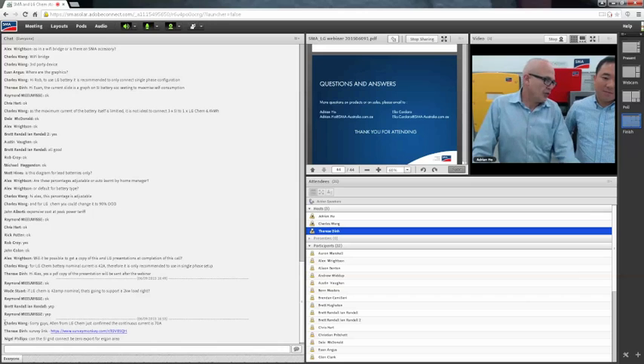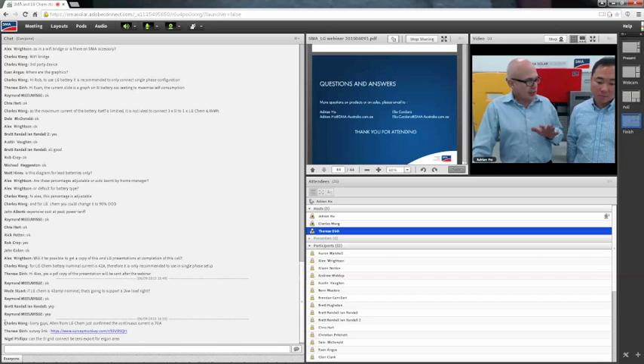On a 3-phase system, if you put a Sunny Island on each individual phase, could you then theoretically put a 12.8 kWh battery bank behind each Sunny Island? Is that possible? Yes, it's possible. So theoretically, if somebody has money to burn and wants 38.4 kilowatt hours, they could do it that way.